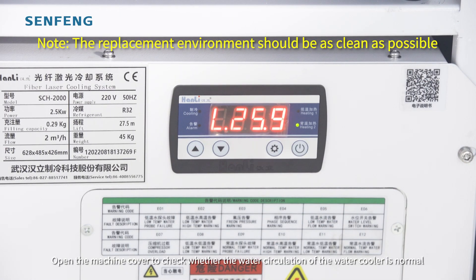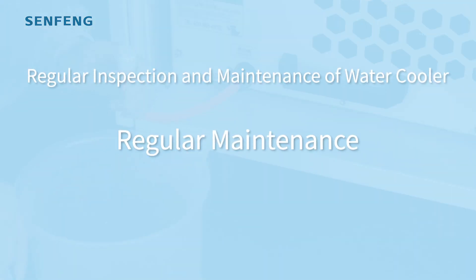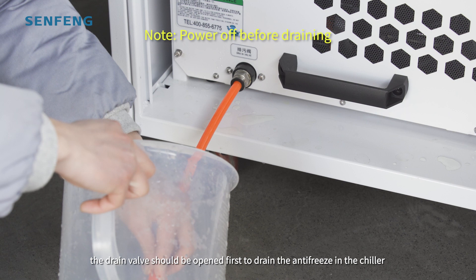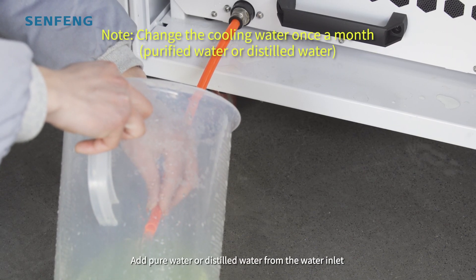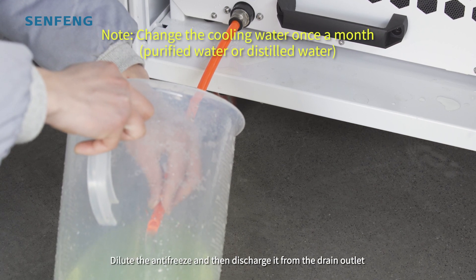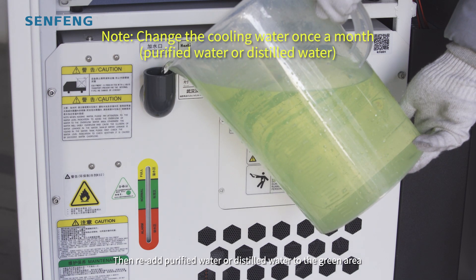Open the machine cover to check whether the water circulation in the water cooler is normal. When the temperature rises, the drain valve should be opened first to drain the antifreeze in the chiller. Add purified water or distilled water from the water inlet and start the machine for circulation. Dilute the antifreeze and then discharge it from the drain outlet, repeating 2 or 3 times. Then re-add purified water or distilled water to the green area.